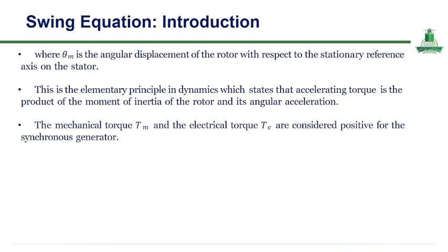The swing equation is a fundamental relation used to describe the dynamic behavior of a synchronous generator. In this equation, theta m represents the angular displacement of the rotor with respect to a fixed reference axis on the stator. It is based on the basic principle of rotational dynamics, which states that the accelerating torque acting on a rotating body equals the product of its moment of inertia and its angular acceleration.